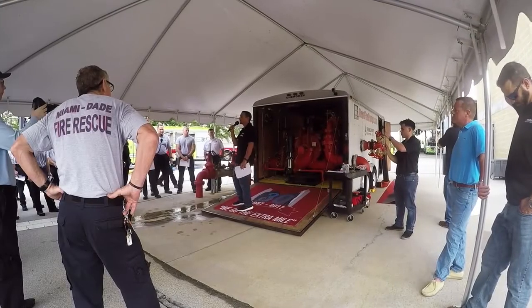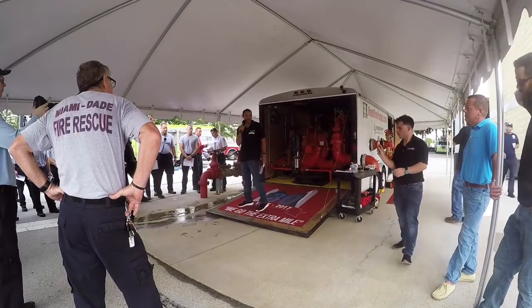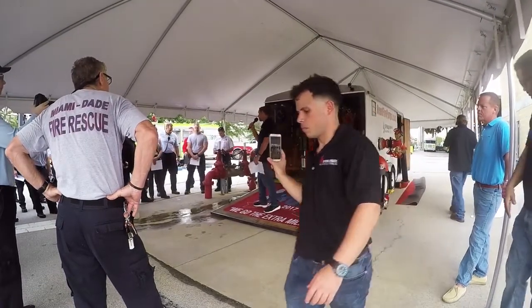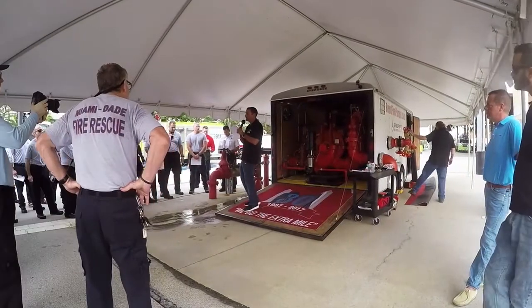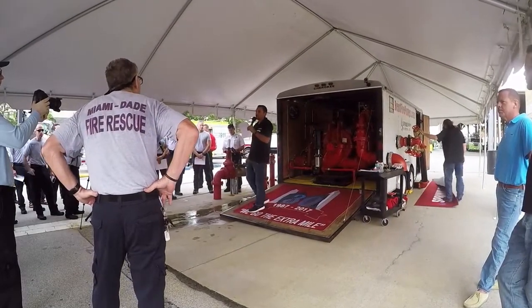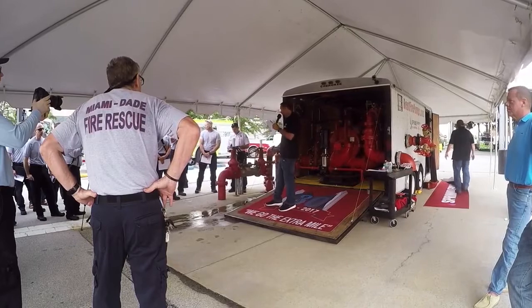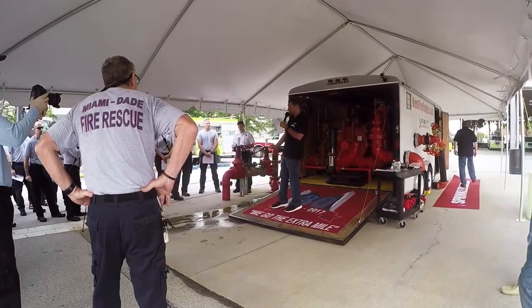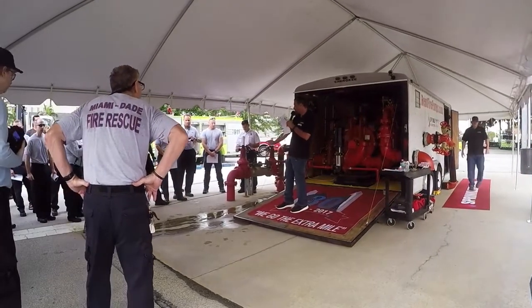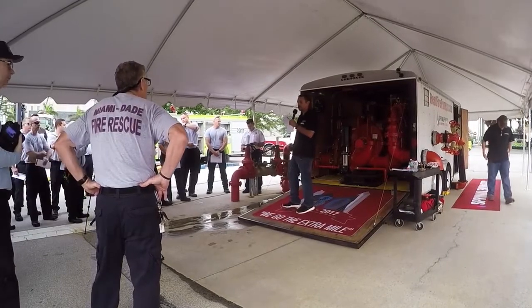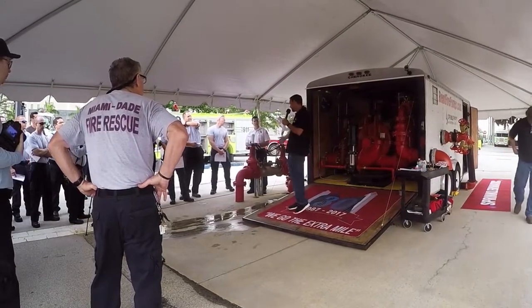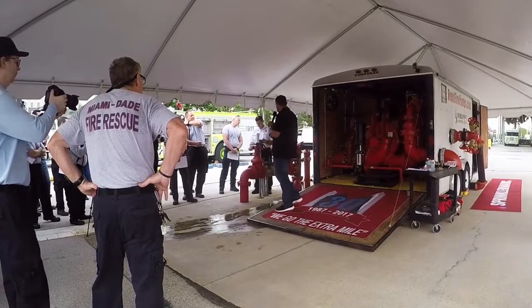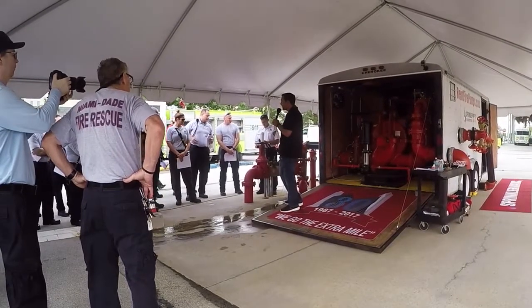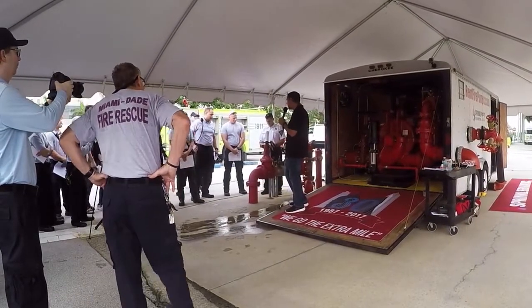I'd like to get started with our system, okay? And our system starts with the city water main, okay? We have a dedicated water service that goes into any building, and that starts, depending on what municipality, from the city water main through the fire backflow. All right, here you can see next to me, this would be considered the fire backflow. This is a DDC VA double detector check valve assembly.